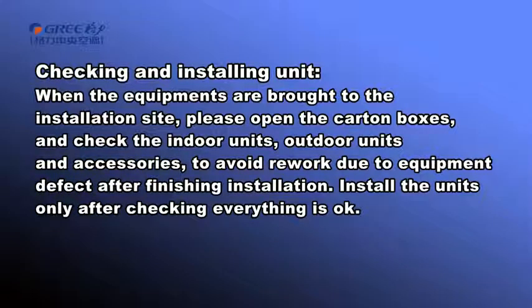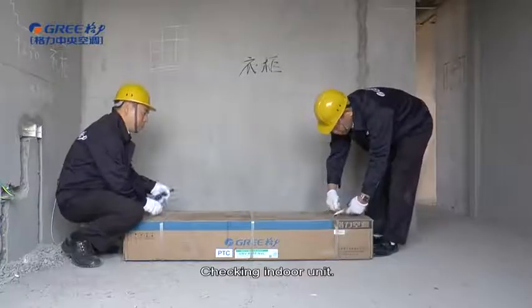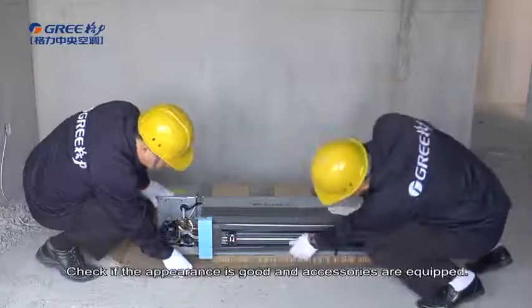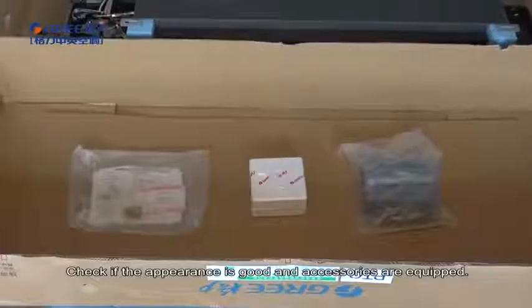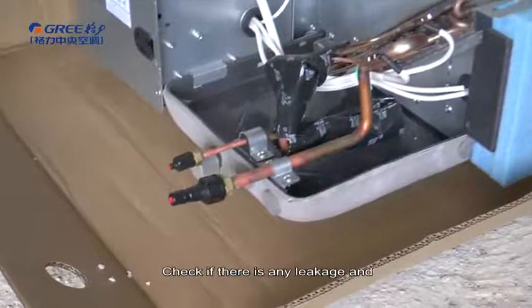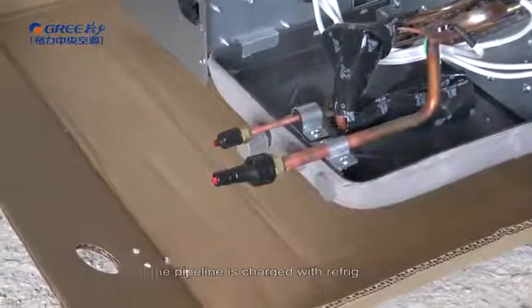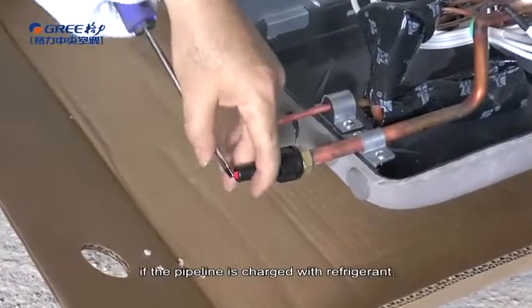Checking and installing unit. When the equipment are brought to the installation site, please open the carton boxes and check the indoor units, outdoor units, and accessories. To avoid rework due to equipment defect after finishing installation, install the units only after checking everything is okay. Checking indoor units. Check if the appearance is good and accessories are equipped. Check if there is any leakage and if the pipeline is charged with refrigerant.